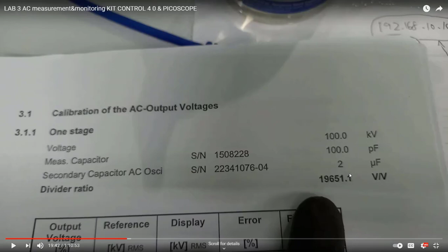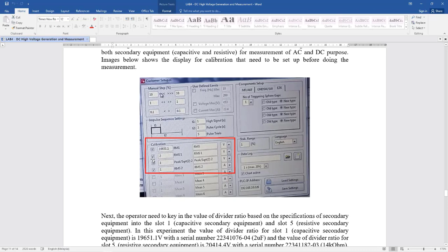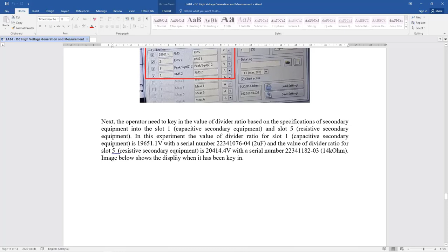We need to refer to the datasheet. This is the datasheet for the AC output voltage capacitor, the secondary capacitor. This is the serial number, and this is the divider ratio value. We need to key in this value to the area here. Same goes for the others. For the next slot, we just need to tick it, and for DC measurement we need to tick slot number 5, because slot number 5 is for DC measurement.